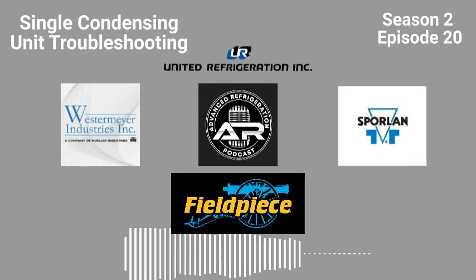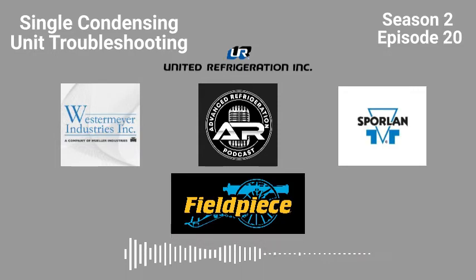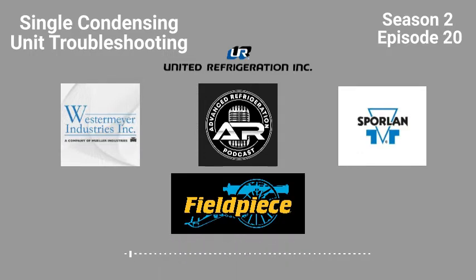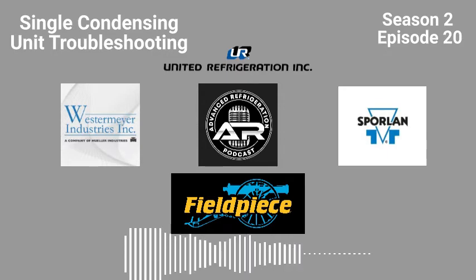I have tons of runtime, but like I said, the valves are open 100%. The valves are open 100%. So yeah, I don't think it's a true 100%. Now that I'm going about this a little more, it's a pulse valve issue.